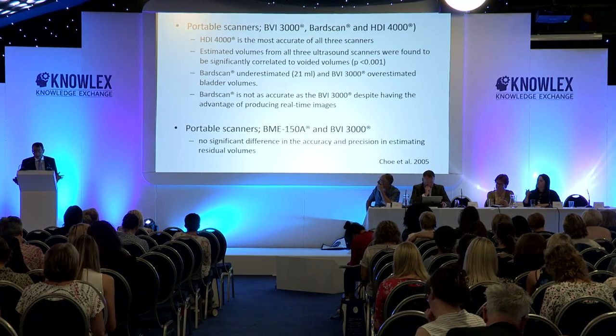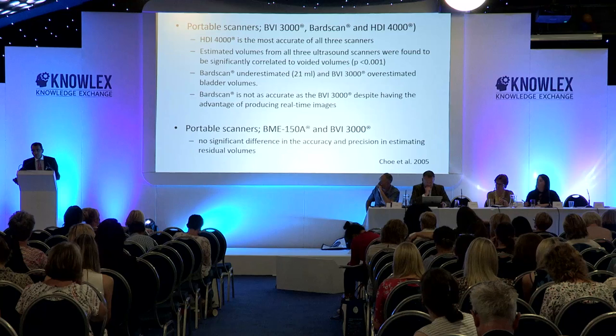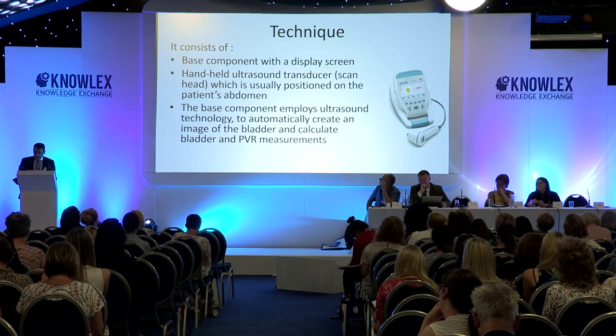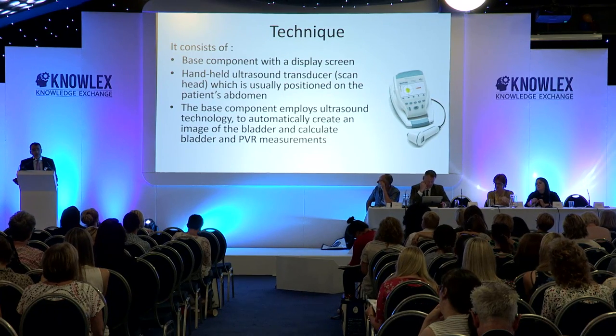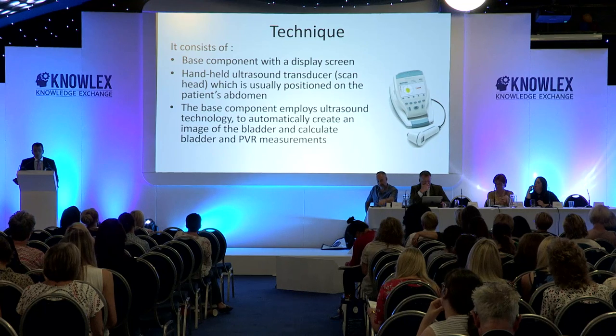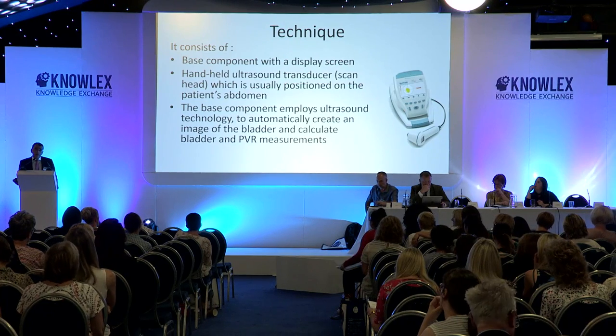Another study comparing different scanners and companies showed no big difference between them; the amount of difference is small. What you also want to look at is the contract with the company, the repair support, and ease of use. Be aware that if you have a bladder scanner in your ward, another ward may borrow it and it may not come back — you need something on a stand that staff are familiar with. The base unit has a screen giving you just the number, connected to the probe.